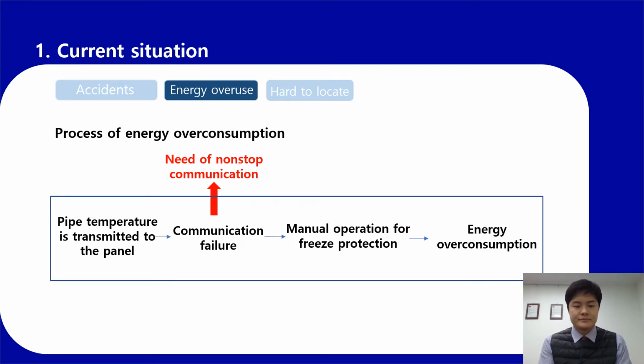During operation, the heating cable overconsumes energy if it does not sense the pipe temperature exactly. The heating cable works when the pipe temperature is lower than the set temperature. If the pipe temperature goes higher than the set temperature, the heating cable is turned off to save energy. But if there is a problem in the sensor which measures the pipe temperature, or especially if there is a communication failure, the temperature information cannot be transmitted from the pipeline to the panel.